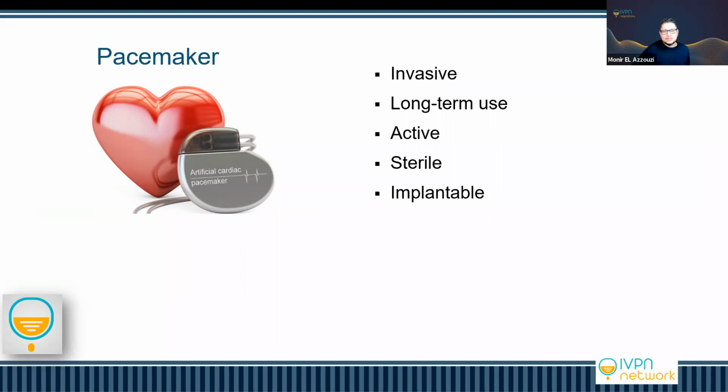And I told you already before that there is one rule that is talking about active devices, because rule 1 and rule 8 is mainly invasive, but here we talk about active implantable device. So here, this rule is for active implantable devices. So again, you can go through the different rules, you just read them, and you define which one is containing any active implantable devices here.